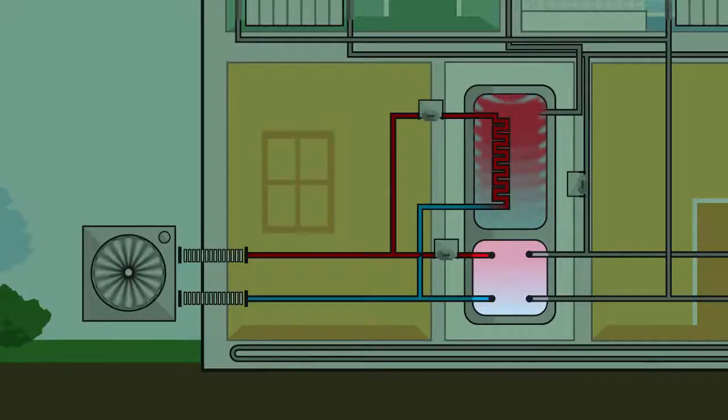It allows for the heat pump to run for longer, reducing the amount of times the heat pump needs to turn on and off. The volume within the vessel assists the heat pump in winter when it carries out its defrost cycle.